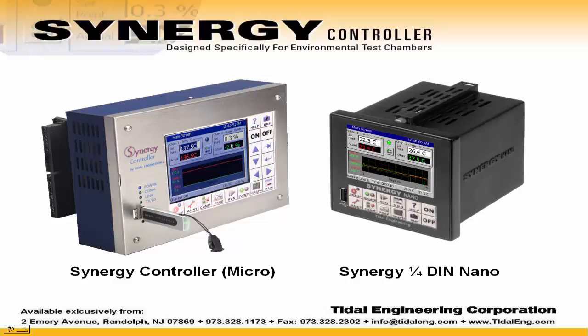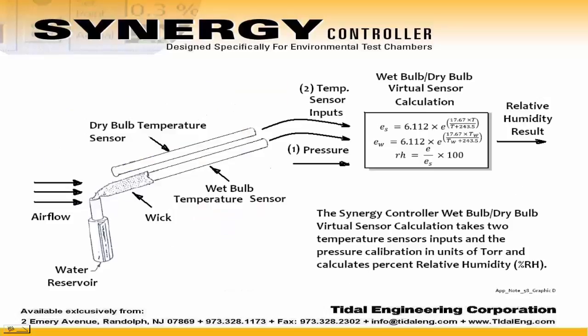The calculation of relative humidity using a wet bulb and a dry bulb thermometer involves the science of psychrometrics. Both Synergy controllers can use a wet bulb and a dry bulb temperature sensor to measure relative humidity as an alternative to an electronic RH sensor. The wet bulb dry bulb is one of the Synergy controller's virtual sensors, where one or more real sensors is processed through an algorithm to produce a calculated process measurement.